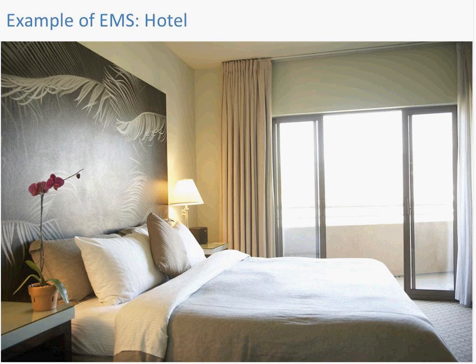Figuring the energy calculations, figuring that rooms are unoccupied between 8 and 4 during the week, and on weekends and holidays it's between 9 and 8, you're really saving about 457,000 kilowatt hours, which figures to about $41,000 per year. The implementation cost with labor and switching out the thermostats would be about $35,000. You're looking at a simple payback of about a year. It's purely theoretical. We haven't had a chance to actually implement this yet, so the time frame could increase substantially, but it's still well within 5 years and under.